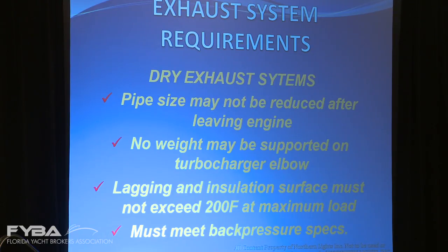This is really important. It contributes a lot to noise that's noticed throughout the boat. So the exhaust system will fall apart if it's not supported that way. A vibration will definitely shake it apart. So no weight can be supported on the exhaust outlet at the turbocharger. And lagging in the insulation can't exceed 200 degrees at maximum load. 200 degrees is a pretty high temperature. It would be nice if it was less than that, but 200 degrees is the absolute maximum. And of course, it has to meet the back pressure specs.